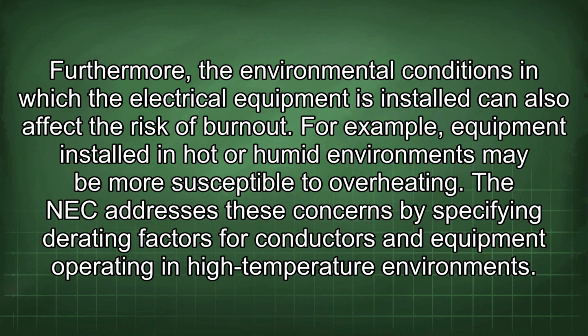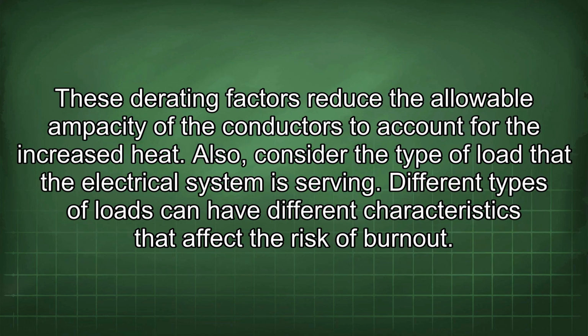Furthermore, the environmental conditions in which the electrical equipment is installed can also affect the risk of burnout. For example, equipment installed in hot or humid environments may be more susceptible to overheating. The NEC addresses these concerns by specifying derating factors for conductors and equipment operating in high-temperature environments. These derating factors reduce the allowable ampacity of the conductors to account for the increased heat.